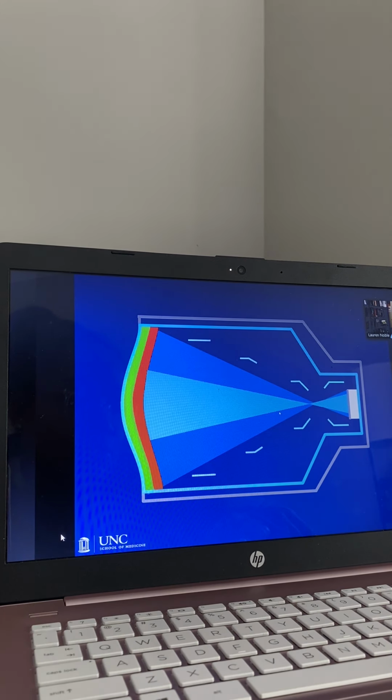And that makes sense, because if we have a smaller area of that output phosphor being hit, we're not going to have as many light photons being produced. So therefore, the exposure has to increase to give us that brightness back. So the plus side of mag mode is better spatial resolution when the radiologist needs to see some better sharpness.